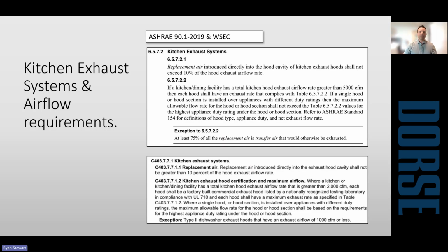So what does that say about exhaust airflow for commercial kitchen hoods? I've listed on top the ASHRAE 90.1. I'm going to reference the Washington State Energy Code. I think that applies to more of the projects here. But basically it says if the total exhaust CFM for the hoods is greater than 2000 CFM, then you need to have a UL 710 listed hood.